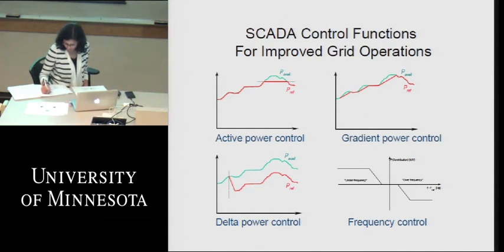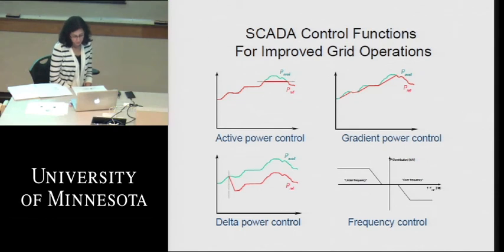We can reserve a little bit of power, hold it back, so that we can do things like under frequency regulation. For frequency regulation, it's easy when you have too much. When the frequency is high, it means you have too much generation, and we just spill wind and lower our generation. But if we're operating at the full power the wind can provide, we can't get more power out of the wind than it can provide. So if we step it back 5 or 10%, like the orange line shows, then we've got some headroom to actually move up and send more power into the grid and affect the type of control you see in the lower right there.